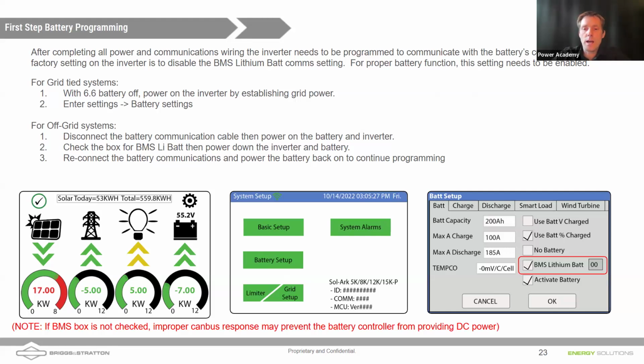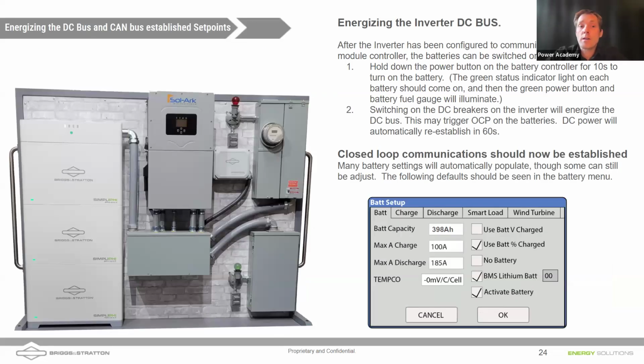So once you've clicked OK there, what that's going to do is tell the inverter to try to communicate over the CAN bus channel. Once that happens, we'll now have a screen which should show the battery capacity. So what's shown on the screen there, 398 amp hours, is what you should see with a stack of three 6.6s. The maximum charge and discharge values shown there are the default values on the Sol-Ark screen. Those are not the values that you might necessarily want. And so we're going to talk about how to program those on the next screen.